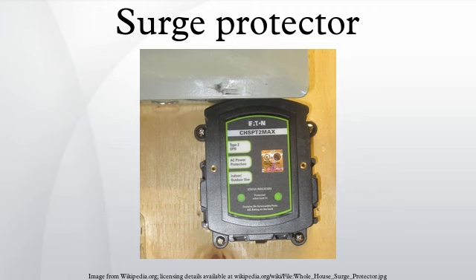Response time: surge protectors don't operate instantaneously. A slight delay exists. The longer the response time, the longer the connected equipment will be exposed to the surge. However, surges don't happen instantly either. Surges usually take around a few microseconds to reach their peak voltage, and a surge protector with a nanosecond response time would kick in fast enough to suppress the most damaging portion of the spike. Therefore, response time under standard testing is not a useful measure of a surge protector's ability when comparing MOV devices.